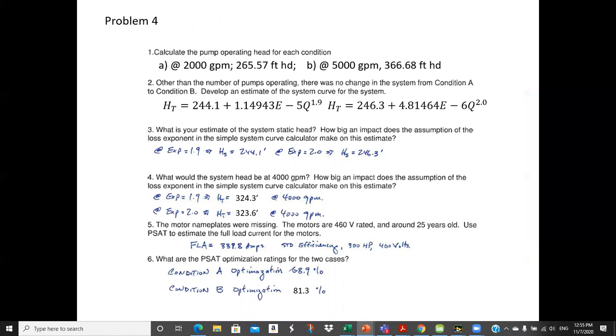What is your estimate of system static head? So we see with 1.9 it's 244.1, with 2 it's 246.3, so not much difference on a system this size. And then if you exercise these equations with 4,000 GPM, you'll see that with the exponent of 1.9, the total head is estimated at 324.3, and with an exponent of 2, it's 323.6. So for all practical purposes, it's about the same thing. Full load amps, it says that the motor nameplates were missing. And so that's one thing that you can do in PSAT pretty easily, estimate full load amps: standard efficiency, 300 horsepower, 460 volts. It's 339.8. I've got the PSAT analysis coming up here in a second.